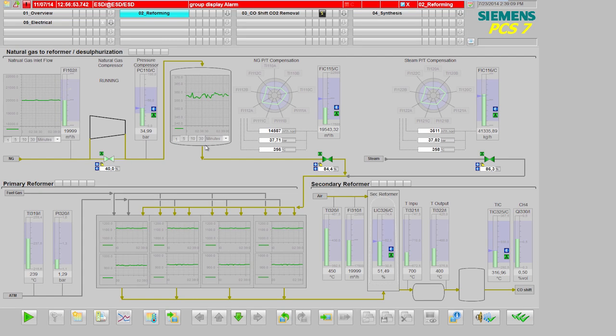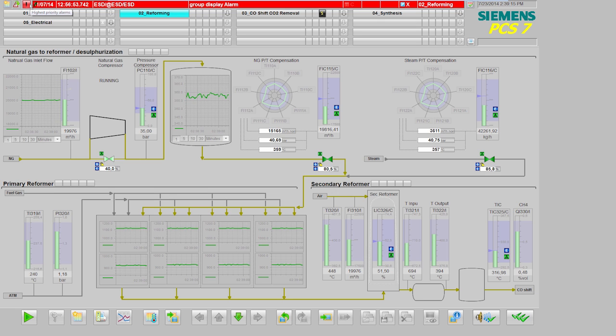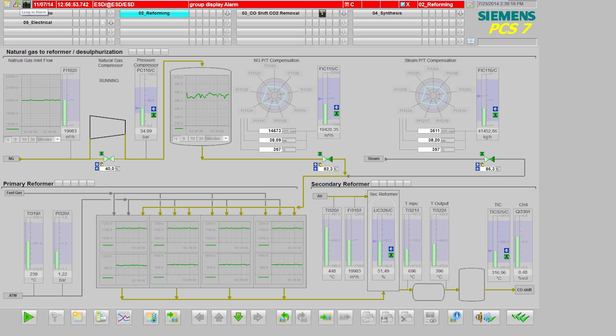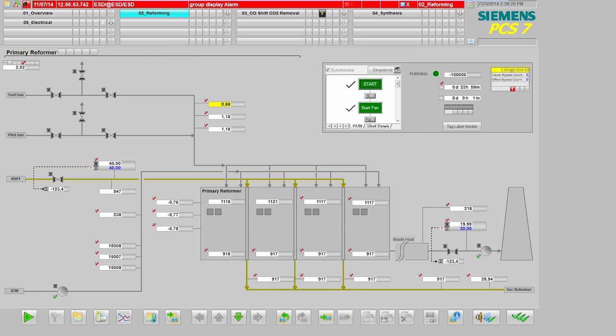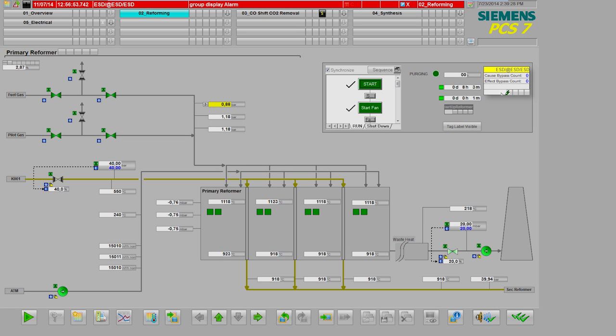I am now in a fertilizer manufacturer's control room, where I can see that an alarm has been triggered by the ESD system. So, I am looking to see what's going on. Loop in alarm takes me to the relevant image and I can see there on the right within the safety matrix that there is an alarm in red.